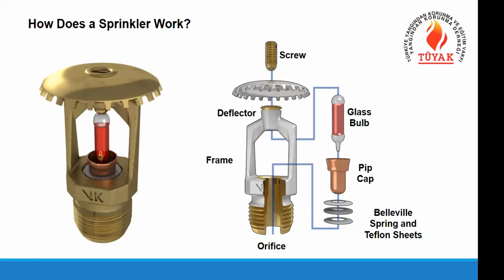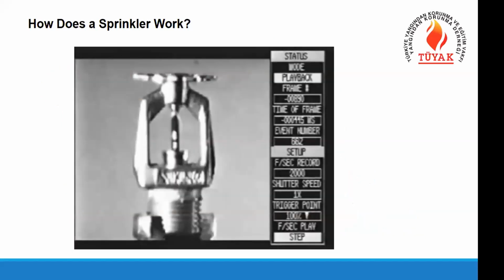So we will see a short video now, which is 2000 times slower than a second. So you will see 2000 frames per second. It activates very fast. So again, we will see how fast it's working. So the waterway is open and the water comes and the sprinkler discharges the water onto the fire. So this system starts to work with the heat activation of the sprinkler.